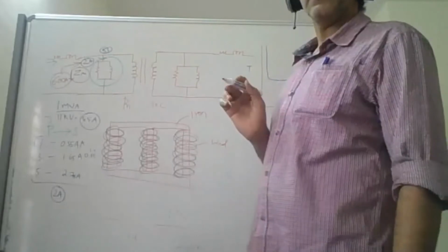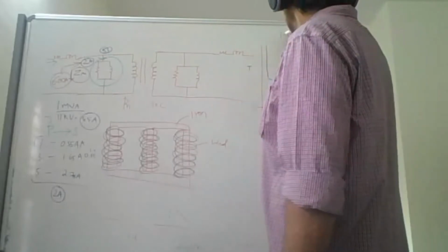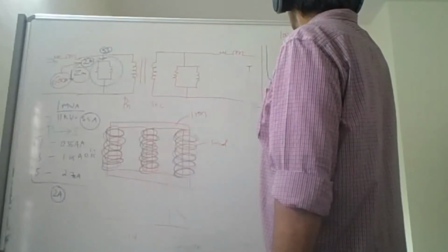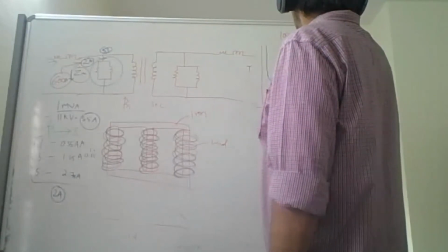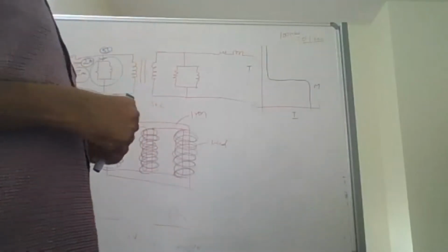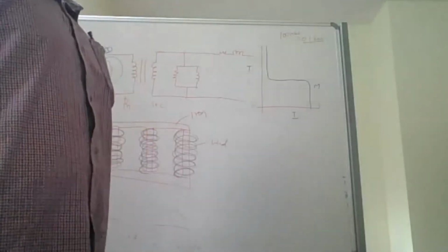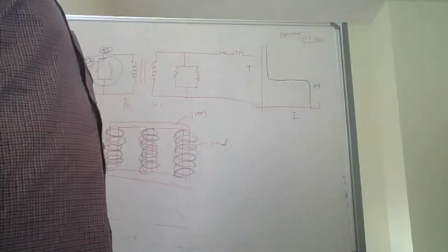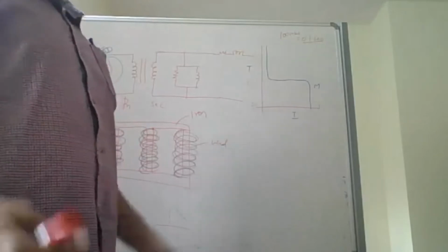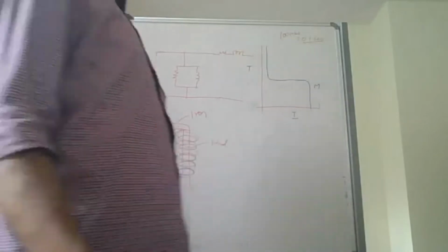100 millisecond. How much? 100 millisecond. I was under the impression it was in microsecond, okay, but millisecond. 0.1 second, 0.1 or 0.2 second. Some 4-5 cycles. See, microsecond is very, very less. It will take 4-5 cycles, whereas your motor is taking 10, 20, 30 seconds. Okay.